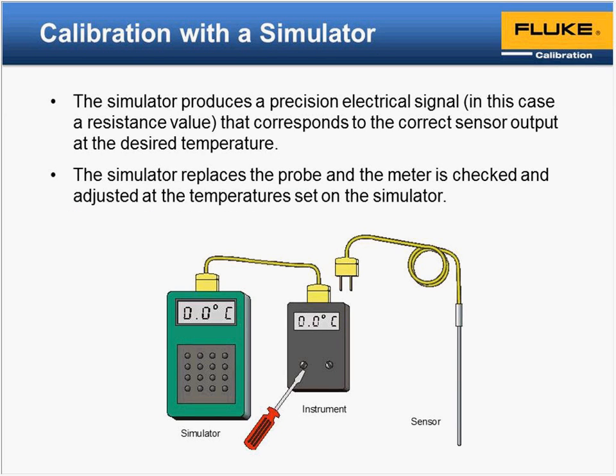So basically, we're going to disconnect the probe and connect our simulator. In this example below, I can see it's usually just a pretty simple connection. We're simply unplugging and then reconnecting. Again, really simple. The only thing to consider is that with thermocouples, you do have to have the appropriate type of plug. Again, if you're working with K, J, T, that can give you a little bit of trouble, but there are universal ones, which I think most can work well with. So again, just things like that to keep in mind on the simulator side when you're making the connection.